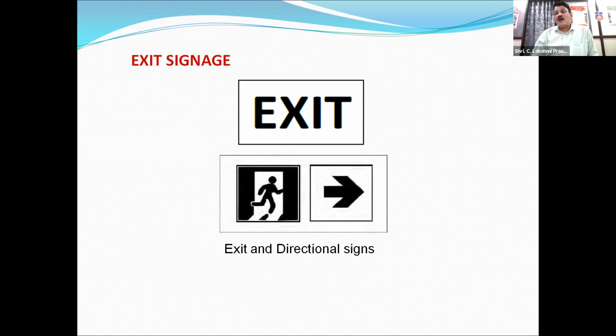Exits are designed for a certain occupant load. So if more people go there, for example, if it is designed for 100 and 300 people are there inside the building, like in cinema theaters, with people waiting 200 and 200 inside. So the exit provided should always be more than what is required. That is very important. If you require, for example, 3 meters and you provide only 3 meters in such buildings, it may not meet the need in many circumstances. So it should be at least 4 or 5 meters, so that it can handle the floating population or waiting people. That has to be taken into consideration.